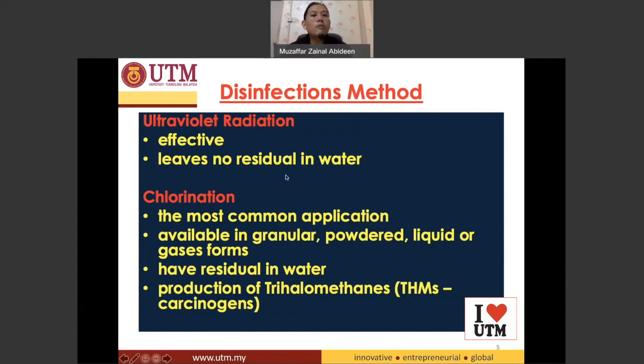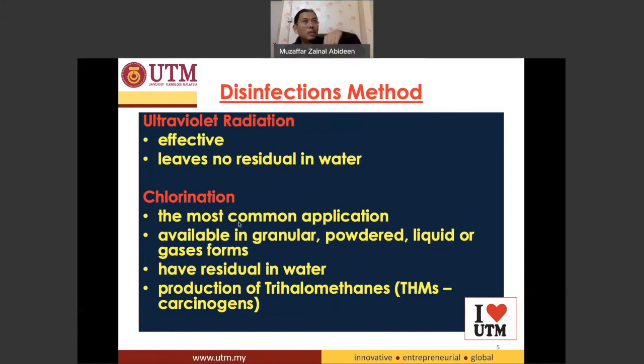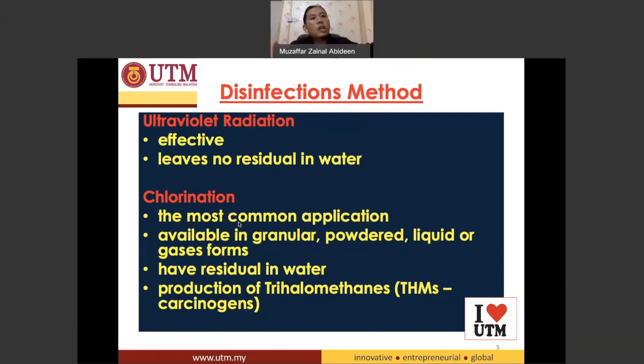Chlorination is the most common application for disinfection. It is available in granular form, powder form, liquid form, and gaseous form. The good thing about chlorine is that once you add it to the water, it will maintain some residual in the water so that it can protect the water all along the piping distribution line.